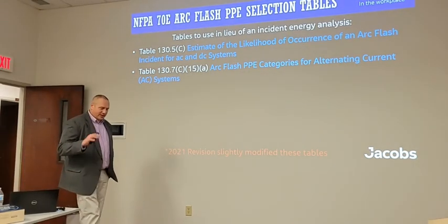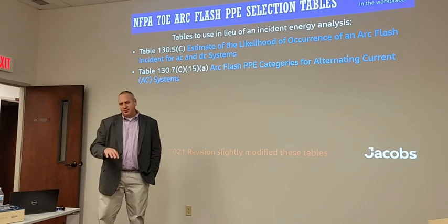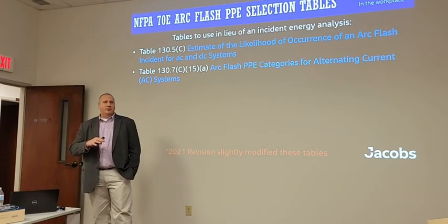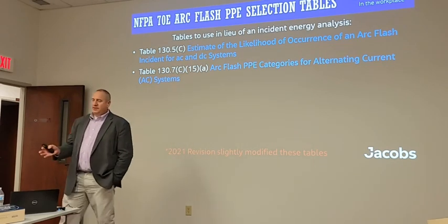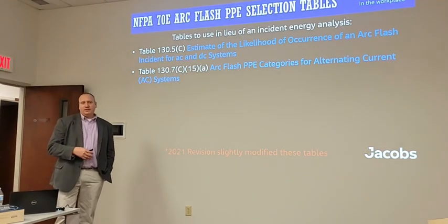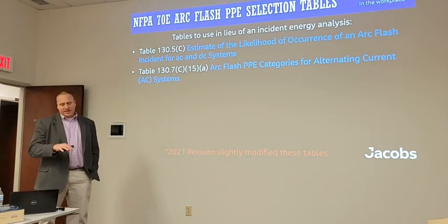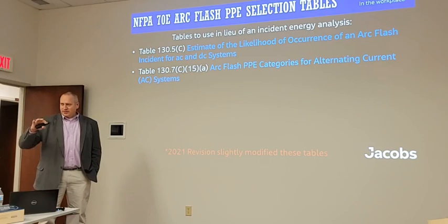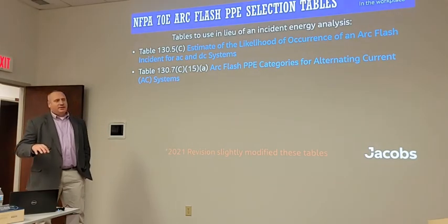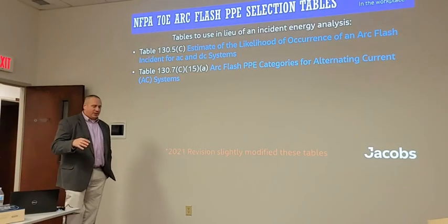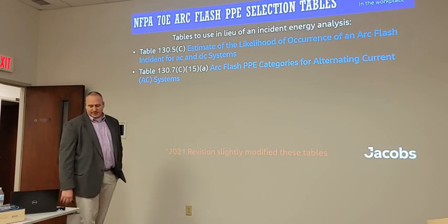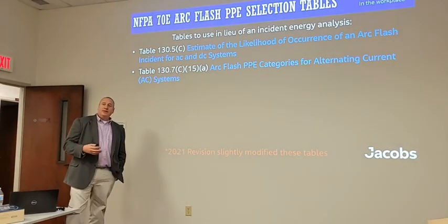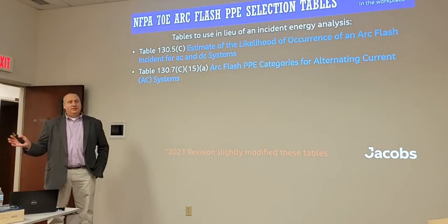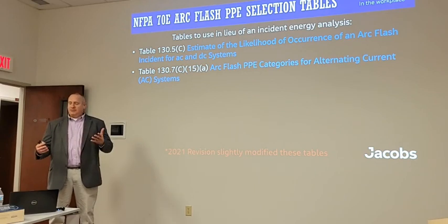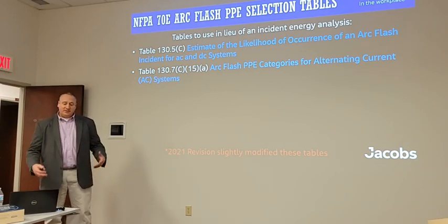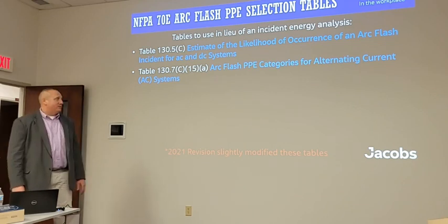And that is where the table lists different tasks that you're going to perform. I'm going to operate a breaker, or I'm going to open a hinged cover. I'm going to rack a breaker off the energized bus. There's a whole lot of different tasks, and then it gives you whether there's a likelihood of arc flash to occur or not given that task. And if the answer is no, then you can fill that out in your risk assessment that the table says there's not a likelihood, then you make a decision whether you want to choose arc flash PPE or not.